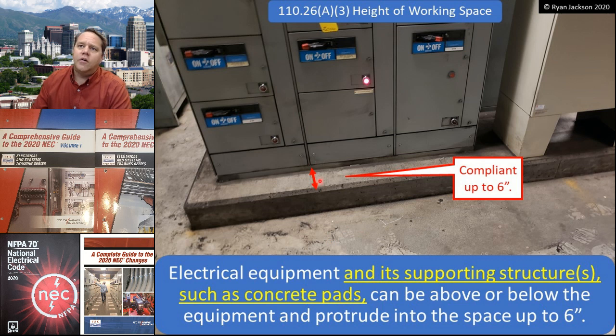And I have a housekeeping pad under it. This complies as long as the housekeeping pad is not more than 6 inches in depth. Now, we could argue that previous versions of the code did not allow housekeeping pads whatsoever, or equally argue that they allowed housekeeping pads of any size.